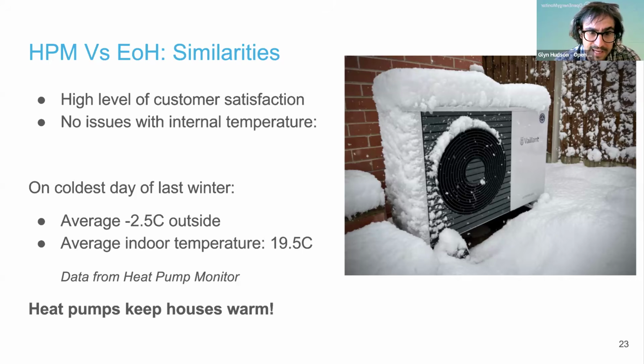The trial reported a high level of customer satisfaction. People were generally happy with the heat pumps, and there weren't any significant issues with internal temperature. We pulled the data from HeatPumpMonitor, and we could see that on the coldest day of last year, where the average temperature dropped down to -2.5 degrees over that day, the average indoor temperature from the heat pumps on HeatPumpMonitor was 19.5. So heat pumps keep people warm, that's quite clear, and there was the same outcome from the electrification of heat trial.